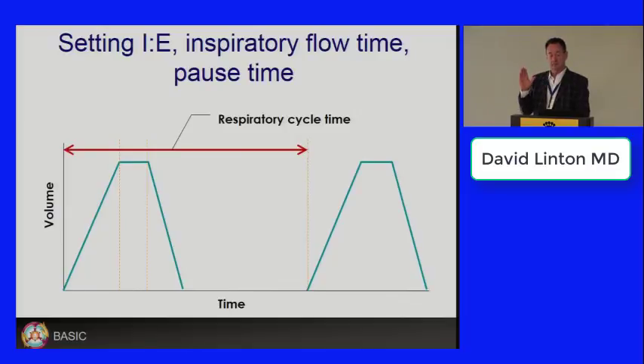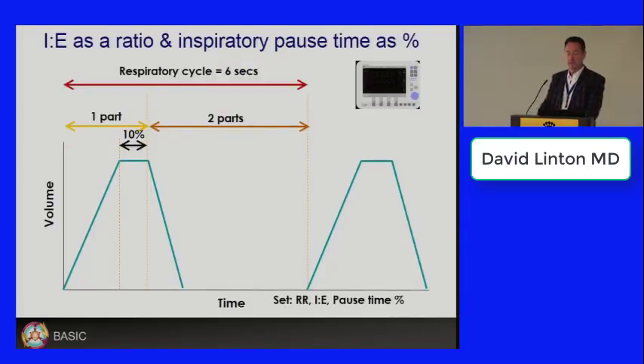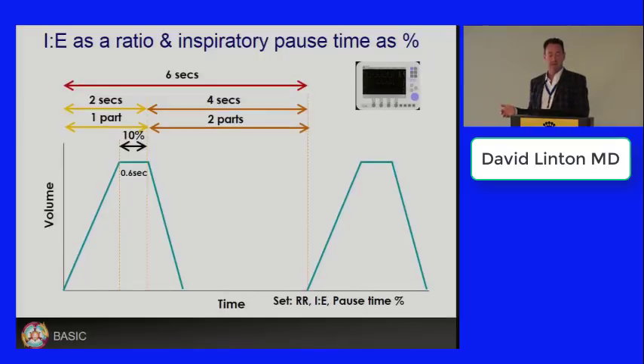And this is the respiratory cycle time. Inspiration, expiration, including the inspiratory flow, pause, and expiration. Now, some ventilators allow you to set the IE ratio and inspiratory pause time as a percentage. Okay? That's all very well if the timing stays the same and the patient's breathing at the same rate.